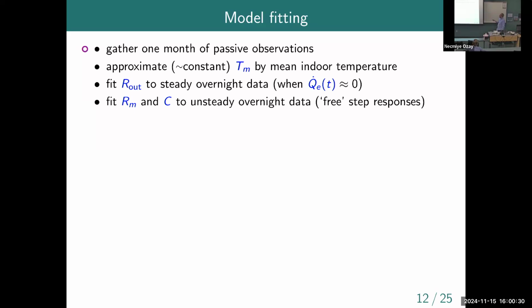Similarly, we use data when this disturbance term is likely very small. We look at the step change data, step response data, that happens overnight in order to estimate the other 2 parameters: the resistance between the indoor air and the thermal mass, and the thermal capacitance of the air, the energy storage capacitance.